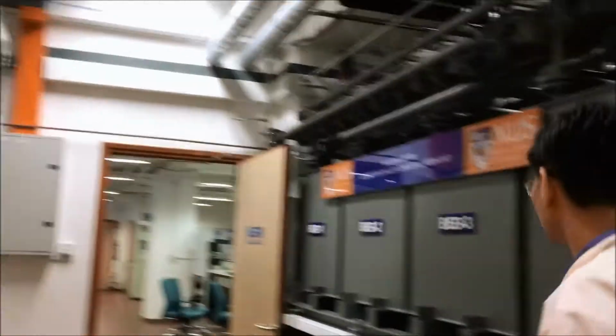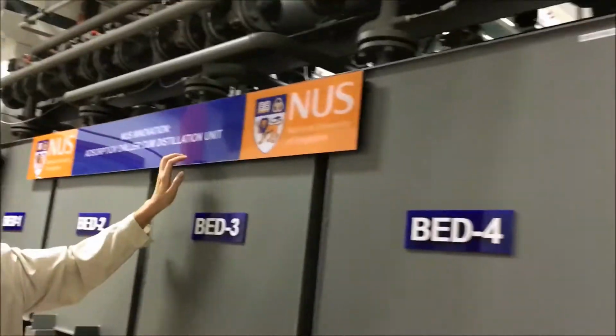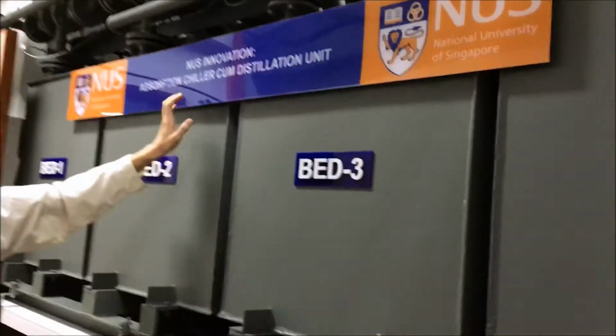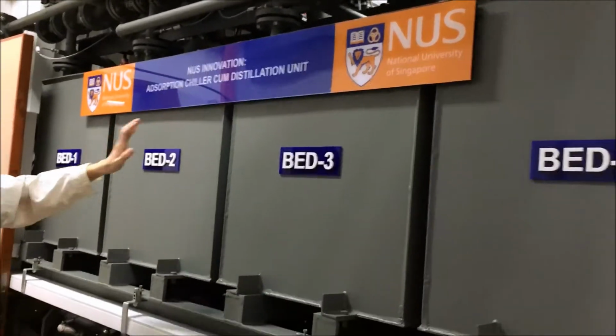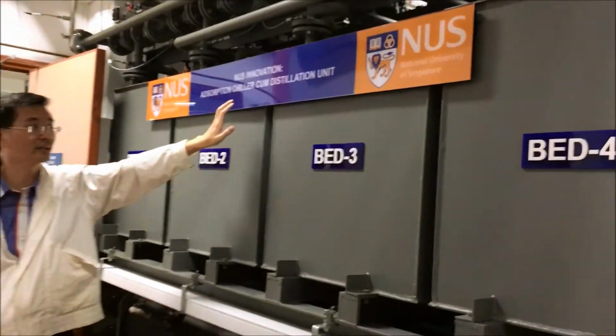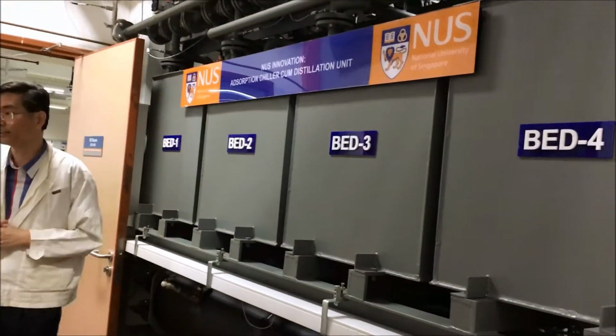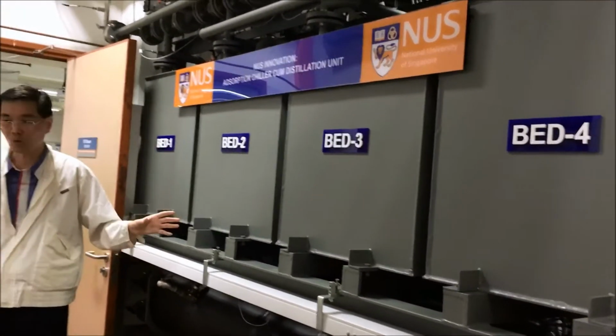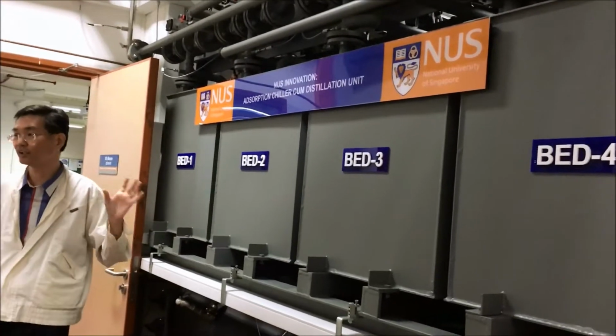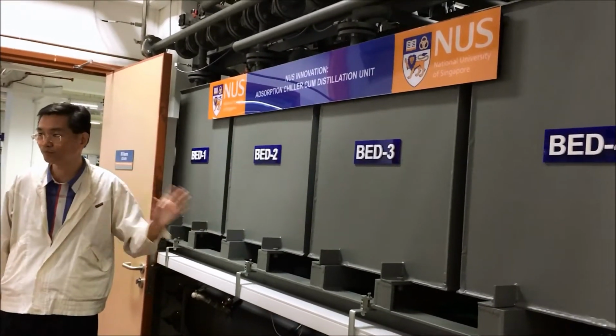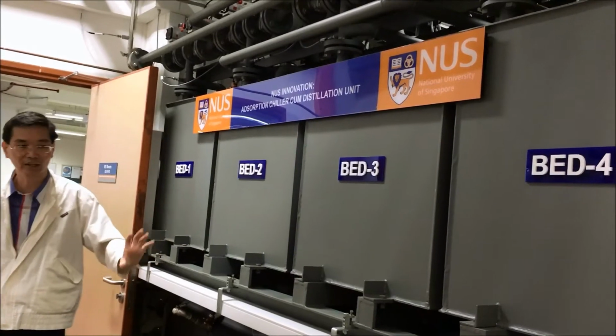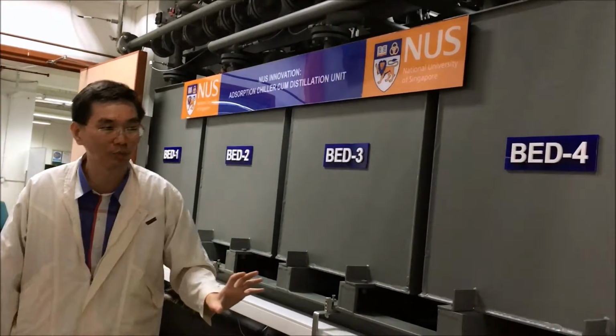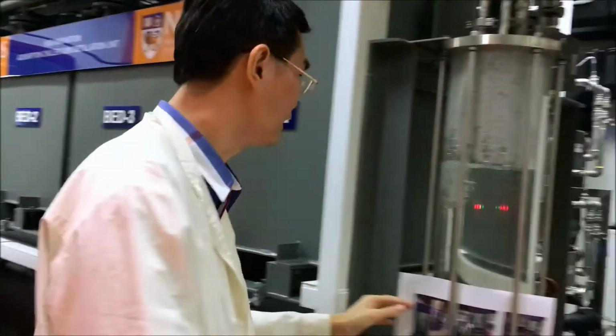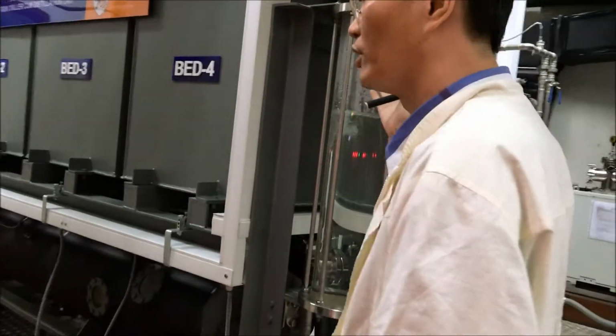The 4-bed 2-evaporator AD chiller. So you can see this very key innovation from NUS, the 4-bed 2-evaporator AD chiller system. Besides producing chilled water, it also doubles up as a distillation unit. So while producing chilled water, any brackish water or seawater that you pump into the system, you can generate very high quality potable water. As you can see from here, the water is continuously producing.